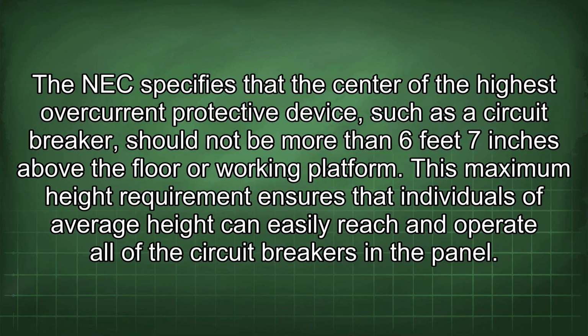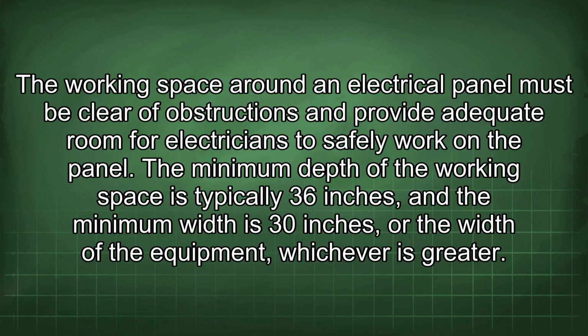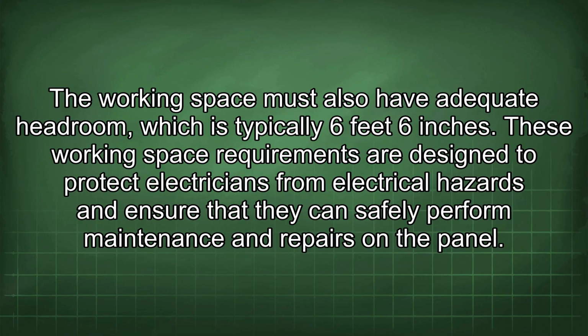The working space around an electrical panel must be clear of obstructions and provide adequate room for electricians to safely work on the panel. The minimum depth of the working space is typically 36 inches, and the minimum width is 30 inches, or the width of the equipment, whichever is greater. The working space must also have adequate headroom, which is typically 6 feet 6 inches.